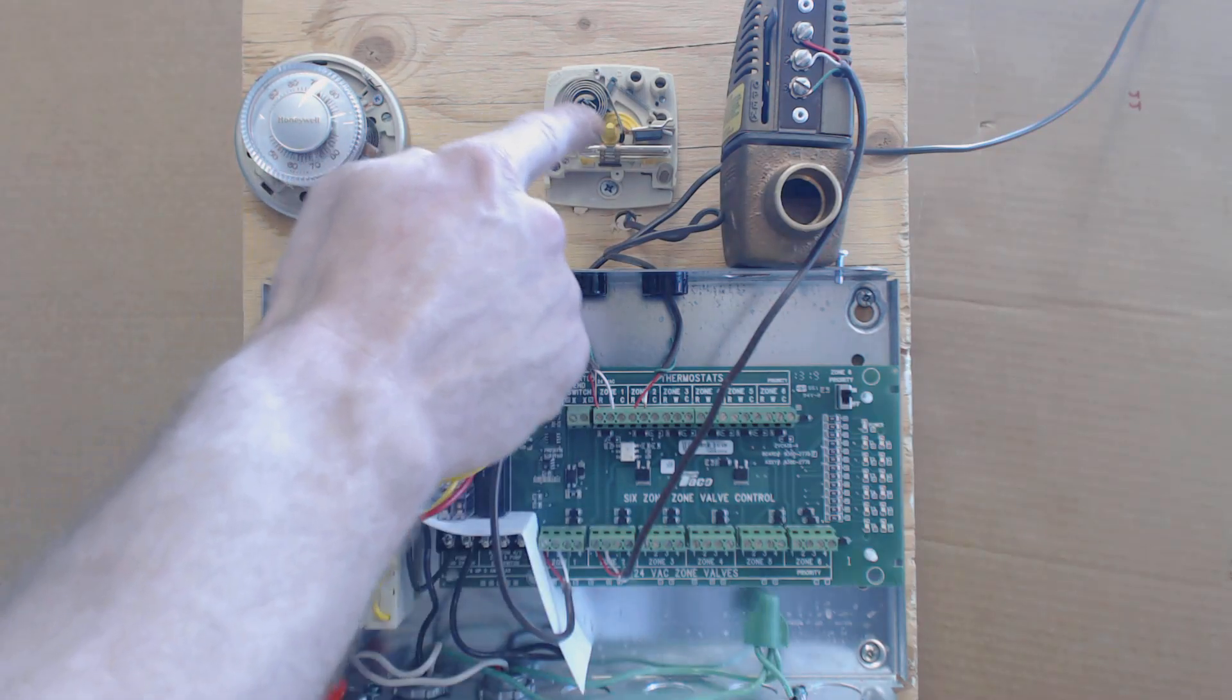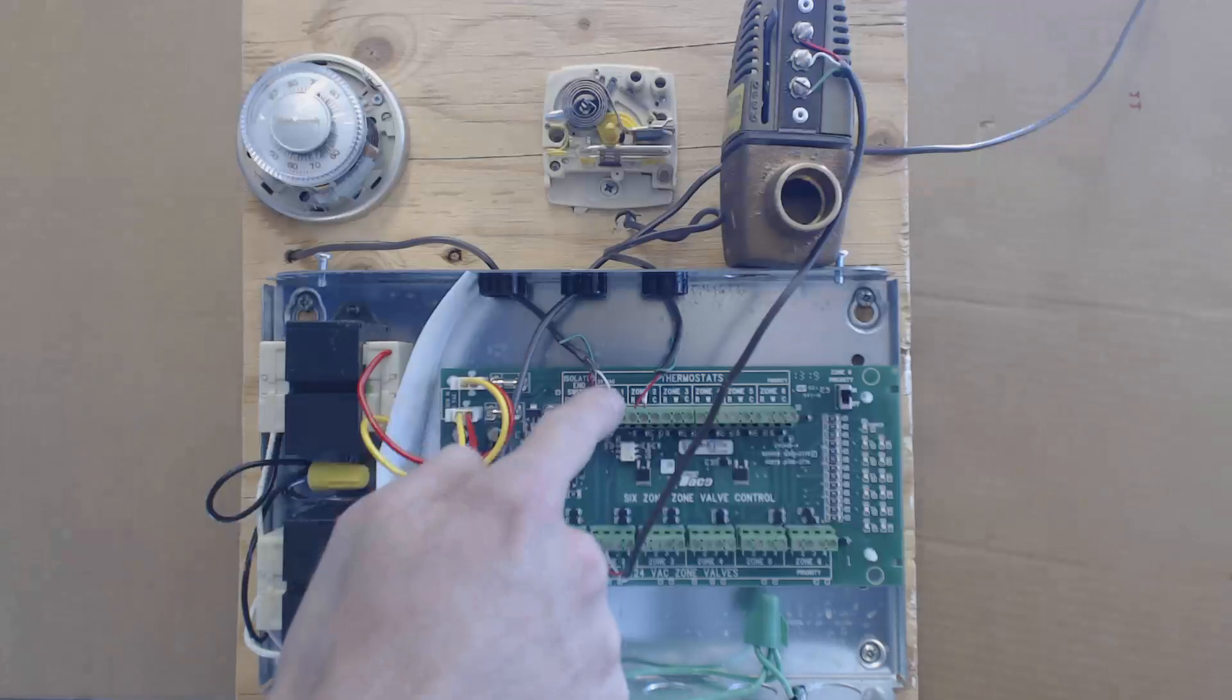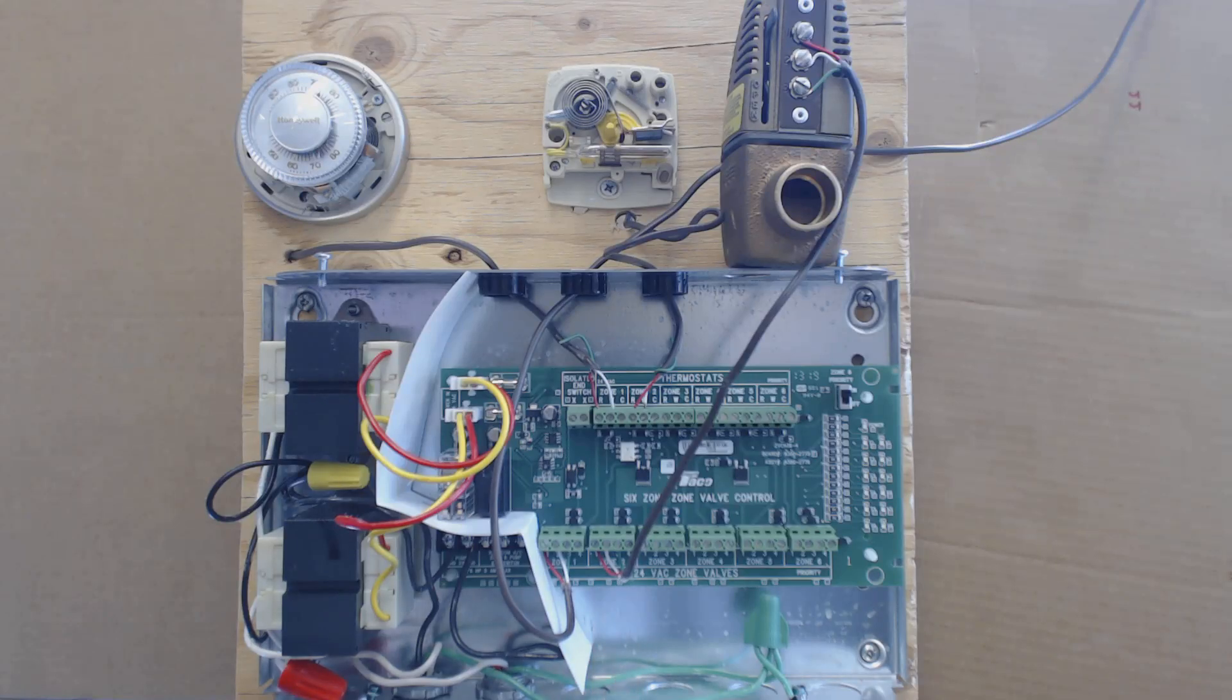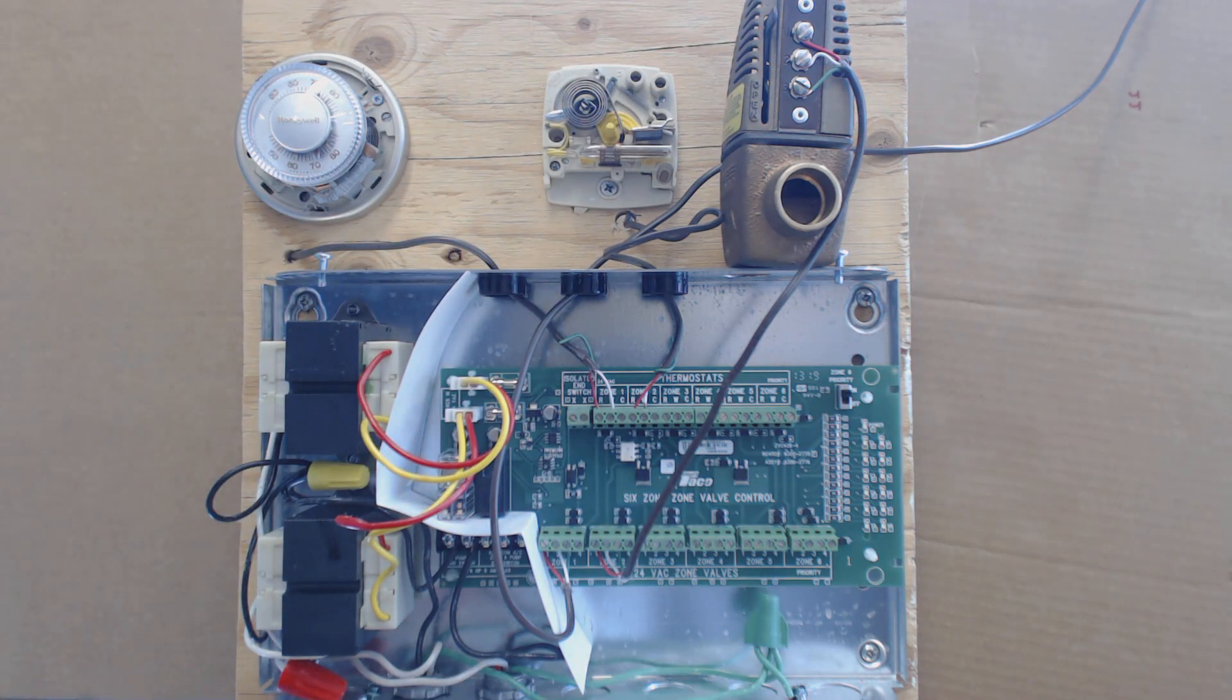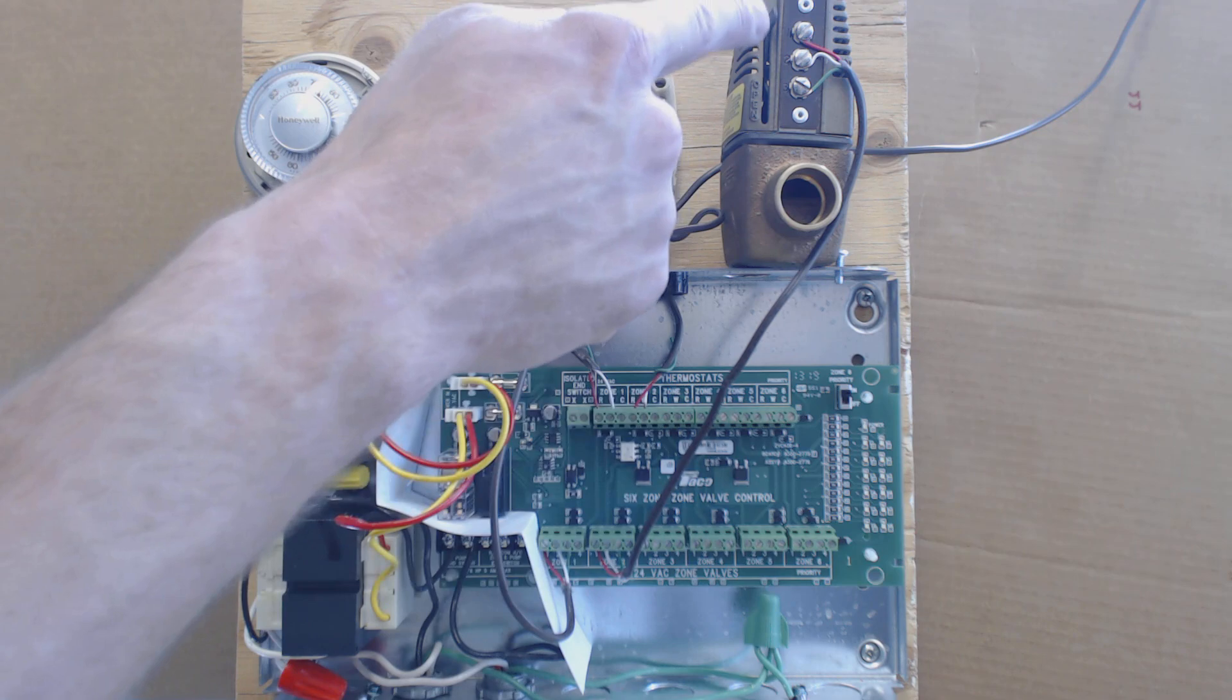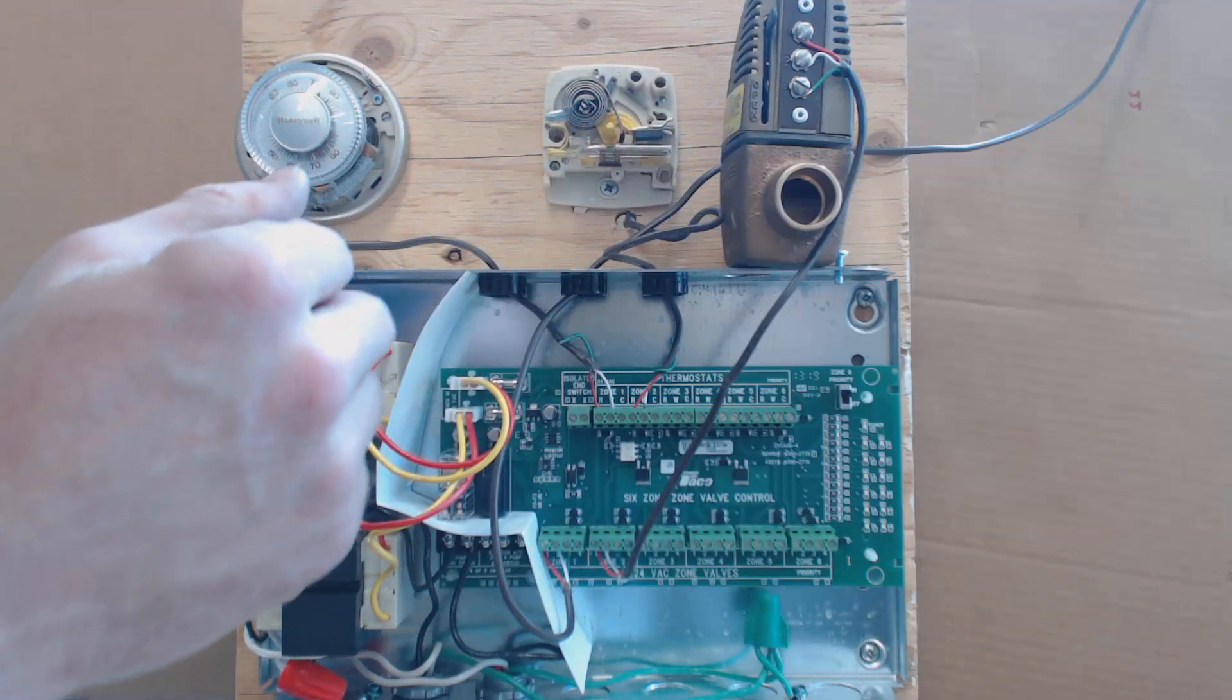So right now we have zone two calling. None of this is powered right now, so you see me pointing at things and everything, but when you have the zone two thermostat calling for heat, W is powered going back to the control board. Down here you have one, two, three, and four. You can wire a three-wire TACO's zone valve, or you can wire a four-wire zone valve like Honeywell's. What you have is one matches right up here with here. One and one, two and two, three and three. So it's very easy to wire this part to the zone valve.